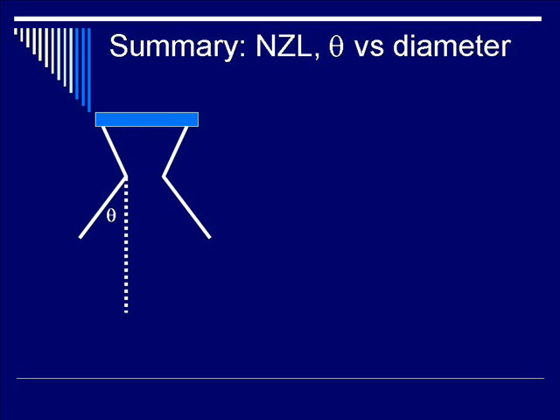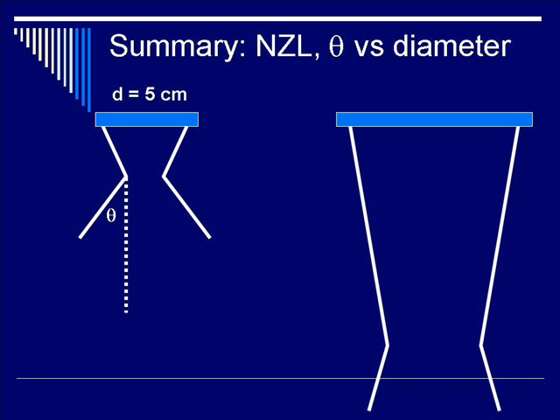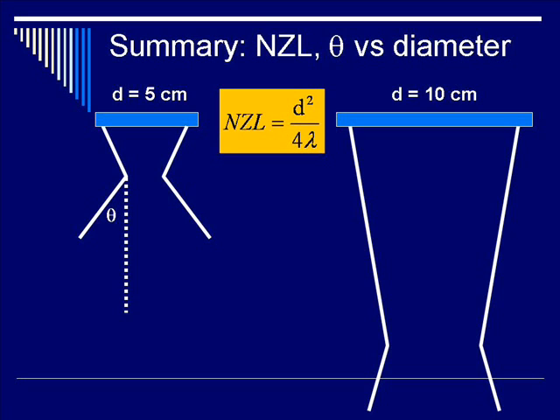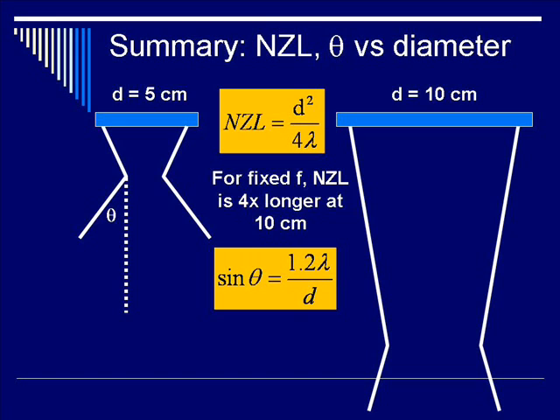Let's look at dependence on transducer diameter. For a given transducer diameter of 5 cm, there is a given NZL and beam divergence angle theta. Increasing D from 5 cm to 10 cm greatly increases NZL while beam divergence decreases. Since NZL is proportional to D squared, doubling the diameter quadruples the NZL — from D equals 5 to 10 cm, NZL increases by 4 times. Beam divergence has only a 1-over-D dependence, so it decreases less dramatically.